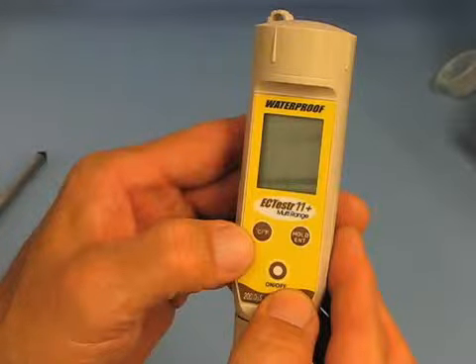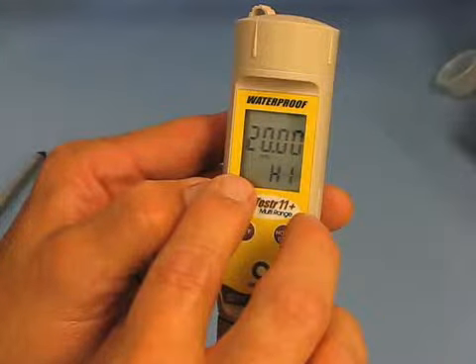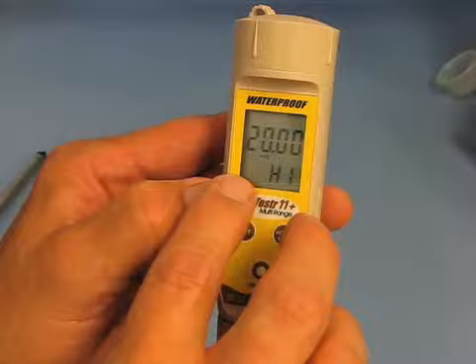The Field Scout EC meter has a variety of ranges that can be used for salinity measurements. We are only interested in the high range for turfgrass systems. To check the range, hold the temperature mode button and at the same time press the on-off button. When set to the right mode, the meter should display the numbers 20.00, a small m and a capital S for millisiemens, and the letters HI. If this is not what the meter displays, you'll need to adjust the range.